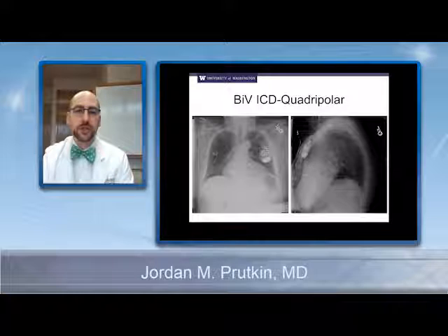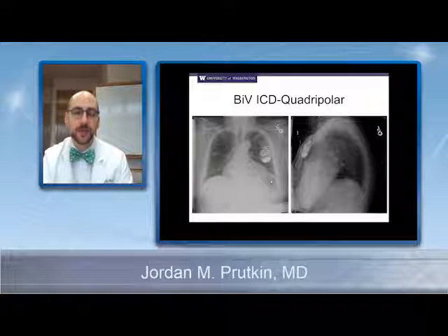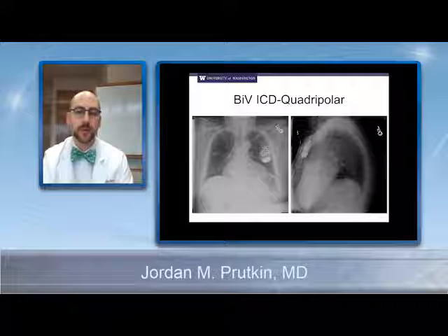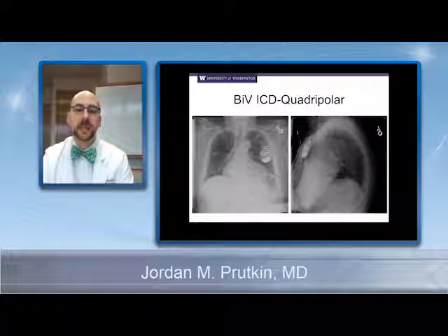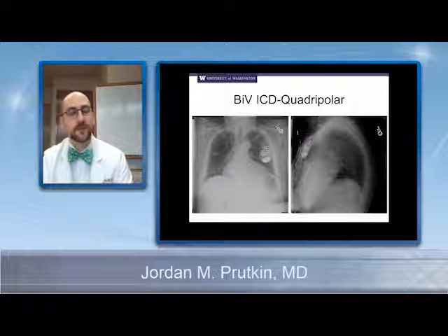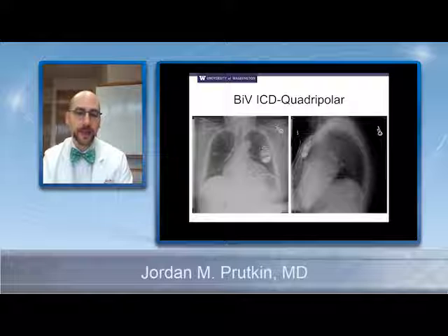One of the other issues is that the left phrenic nerve can run right by the heart where these leads are located, and you can pace the diaphragm unintentionally by pacing the phrenic nerve. It's called diaphragm stimulation. So if you find a set of poles that you're not happy with because they're pacing the diaphragm, for instance, if you're pacing from this pole to this pole, you may find that if you pace from here to here, there's less of an issue with that and less complication associated with the diaphragm stimulation.